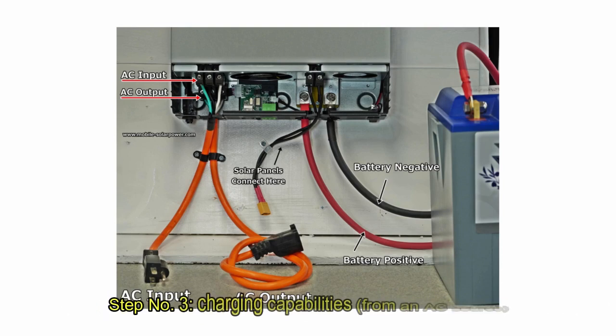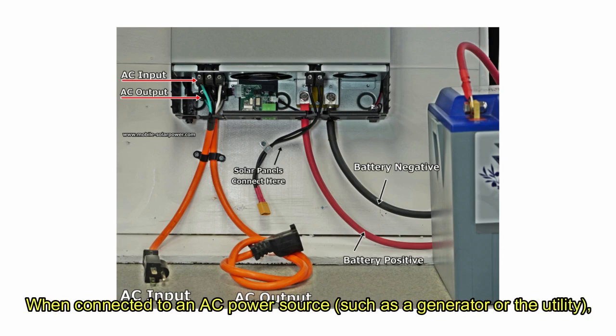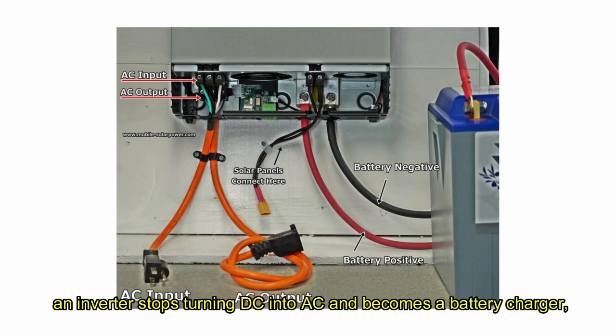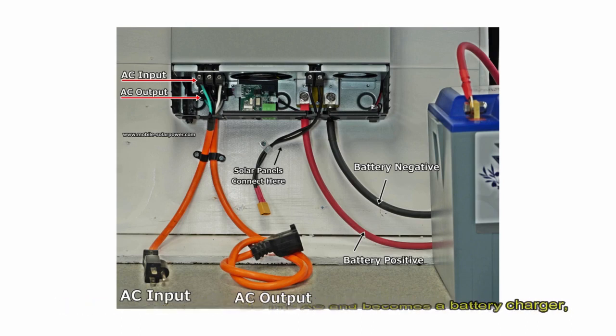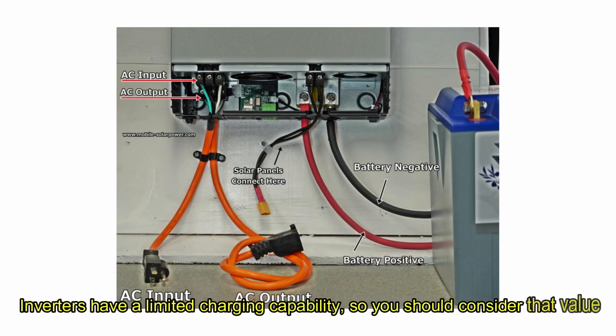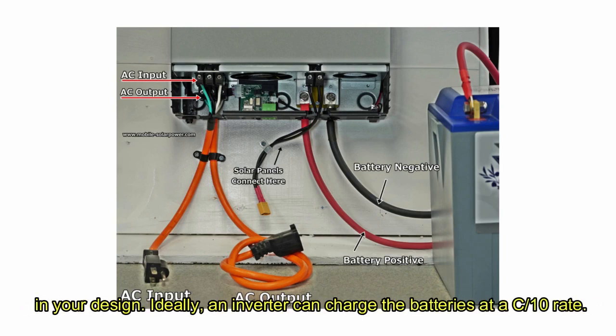Step number three, charging capabilities from an AC source. When connected to an AC power source, such as a generator or the utility, the inverter stops turning DC into AC and becomes a battery charger, taking the AC source and recharging the batteries for you. Inverters have a limited charging capability, so you should consider that value in your design. Ideally, an inverter can charge the batteries at a C over 10 rate.